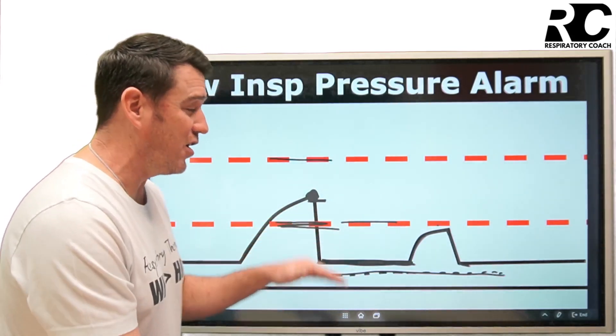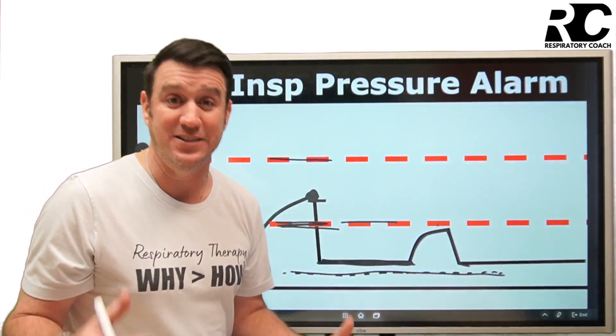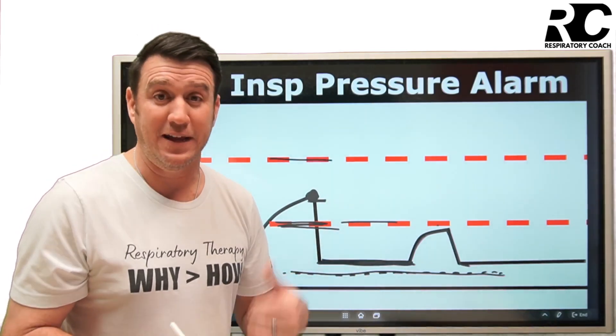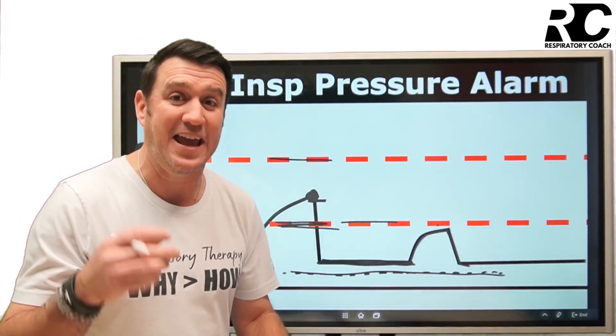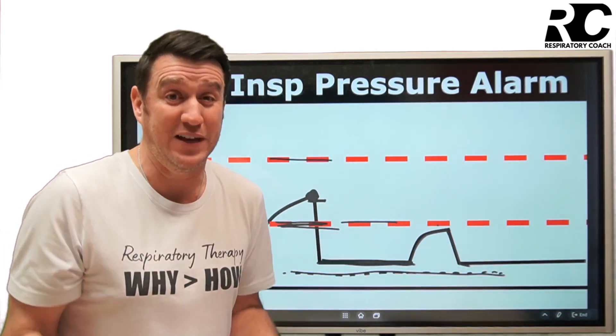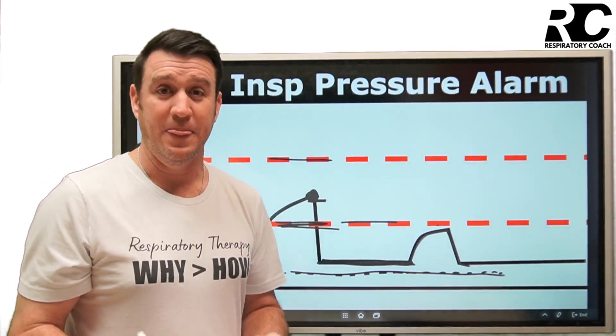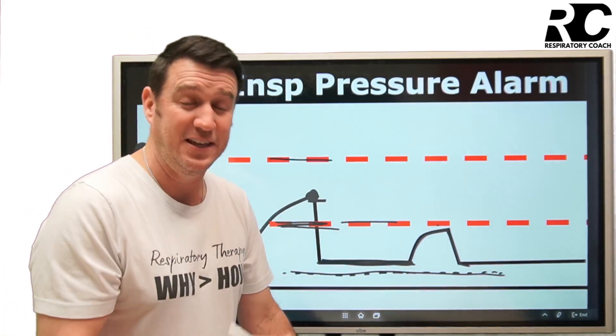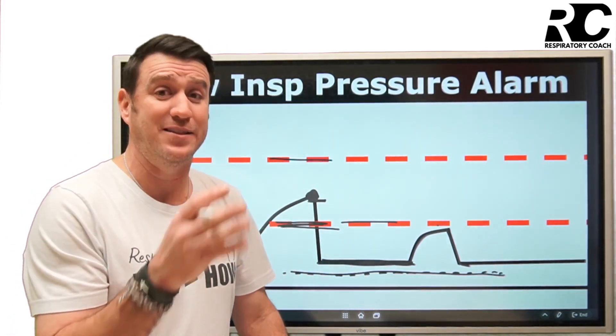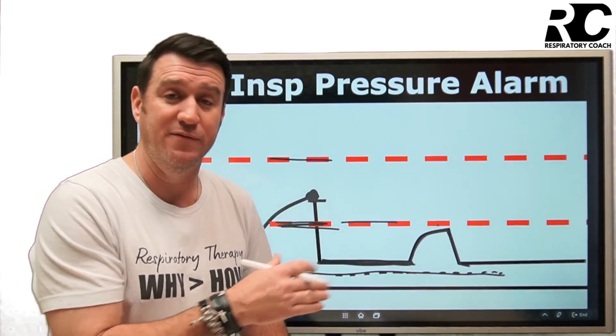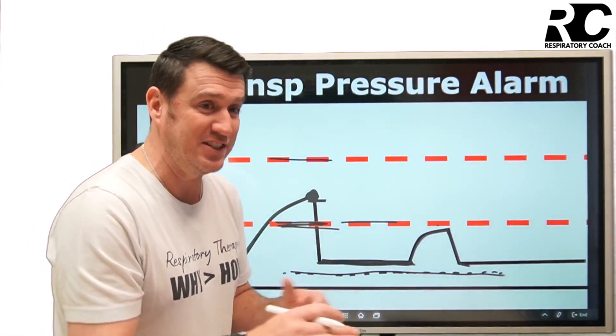Most commonly, if you get this alarm it's because of a leak — somewhere in the circuit or at the airway. Think of it like a nail in a car or bicycle tire: the leak causes pressure to drop. To fix it, you have to find and fix the leak. During mechanical ventilation, a low inspiratory pressure alarm means you need to assess the patient-ventilator interaction for a potential leak. It can occur at the ventilator, within the circuit, or at the artificial airway. For patient safety, start your investigation at the patient.